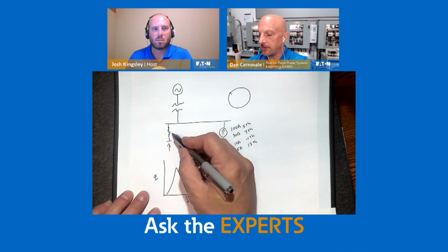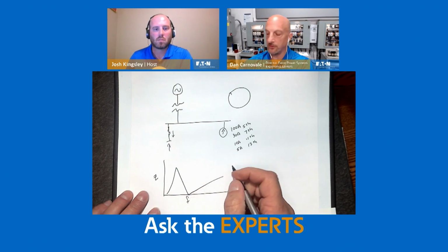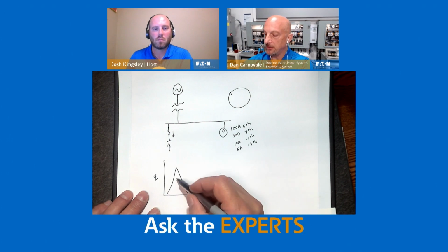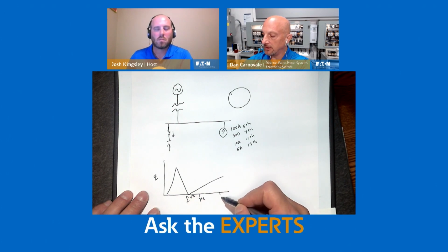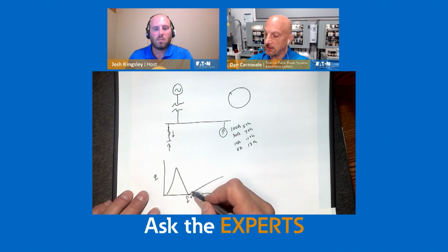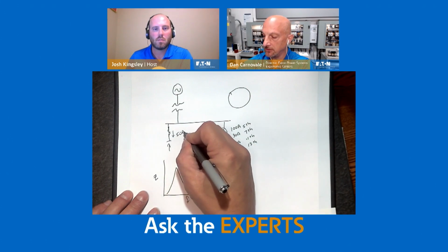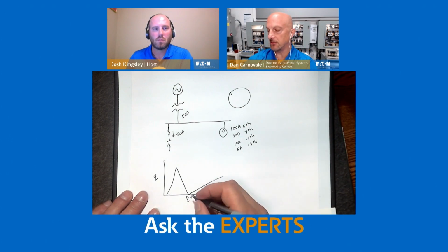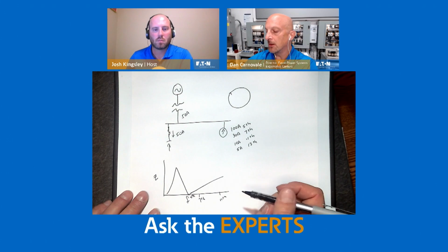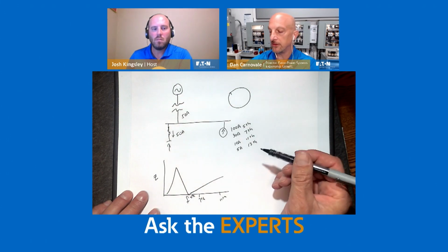If I push current through that path, first of all, only the current that's around this frequency wants to flow through that path, because as you look at the impedance, it's high here and high here. So the fifth harmonic is here, seventh is here, say 11th is here. You're going to get a decent amount of fifth through it. So maybe instead of 100 amps going there, maybe you have 50 amps here and 50 amps there. And then you would determine the losses in that, which is going to be minimal because that resistance is fairly small. But you're not going to get rid of much of the 7th, 11th or 13th, so they're going to still want to flow back in the system.